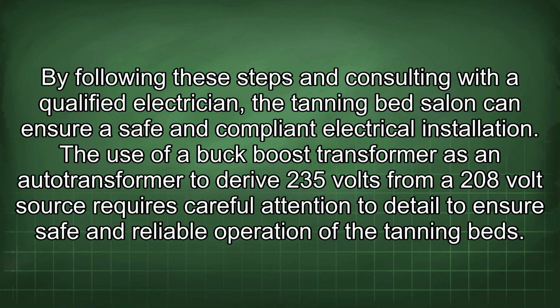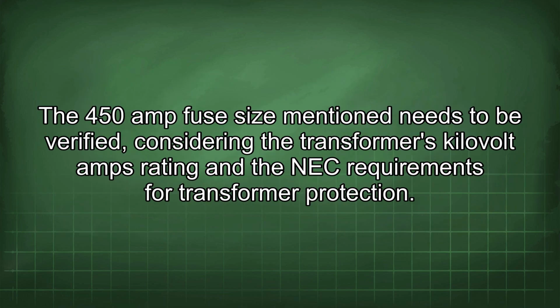The use of a buck boost transformer as an autotransformer to derive 235 volts from a 208 volt source requires careful attention to detail to ensure safe and reliable operation of the tanning beds. The 450 amp fuse size mentioned needs to be verified, considering the transformer's kilovolt amps rating and the NEC requirements for transformer protection.